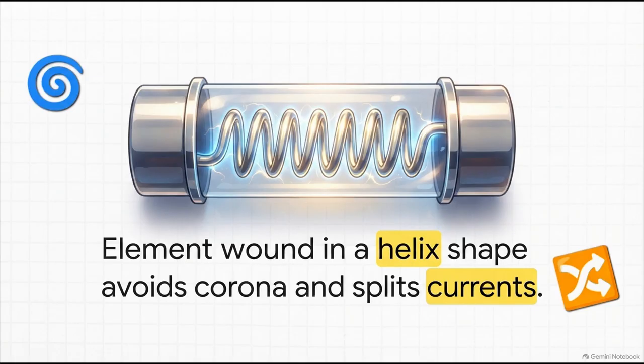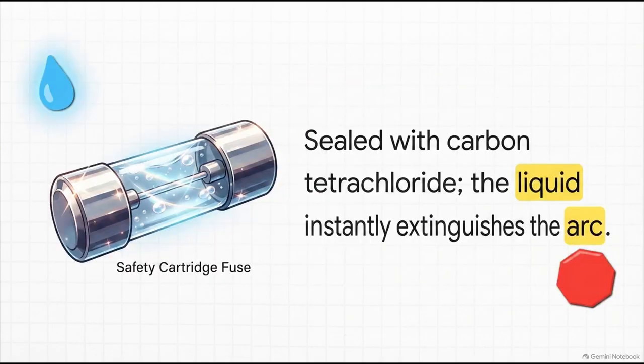So how do you bypass the corona effect? Elegant geometry. The fuse element inside is specifically wound into a helix shape, which successfully avoids the corona effect at those higher voltages. It also utilizes 2 parallel elements, one with low resistance for your everyday normal current and one with high resistance. When a fault hits, that low resistance wire blows out first, safely knocking down the short circuit current. The second solution shifts from geometry to some really fascinating chemistry, the liquid-type high-voltage HRC fuse.